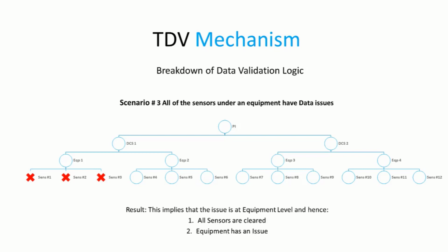Moving on to scenario number 3, if all the sensors under an equipment have data issues, what does that imply? It means the issue is at the equipment level and not at the sensor level. Hence all sensors are cleared and the equipment has the issue.